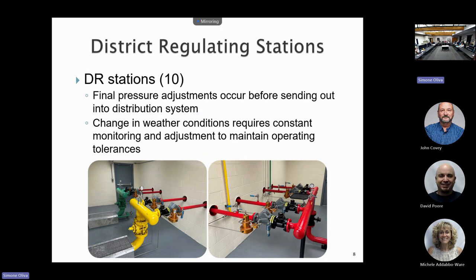This is our Dunham Street station. The red piping is our 60 MAOP system, what we call high pressure in town. We have our high line, which runs from Mohegan Park all the way out - Route 2 used to be the feed out to Foxwoods, ending at Lot 10. The red denotes our high pressure system, goes through the wall after the regulators, and the last regulator adjusts the pressure. We have green for our low pressure system, yellow for our intermediate system, and it goes out into our system. Everything's color coded, and our GIS mapping is exactly the same. Most of the stuff feeding our standby generators is all yellow, that's all low pressure gas - standard colors in the industry.